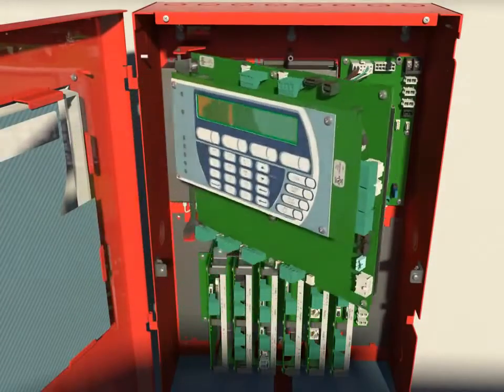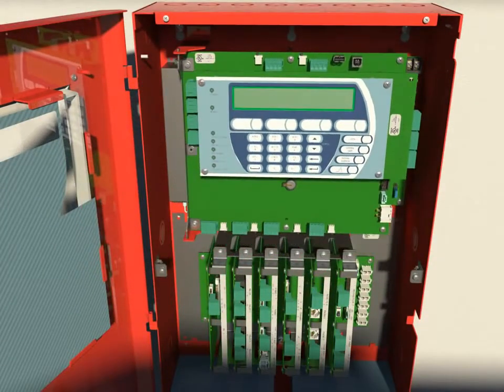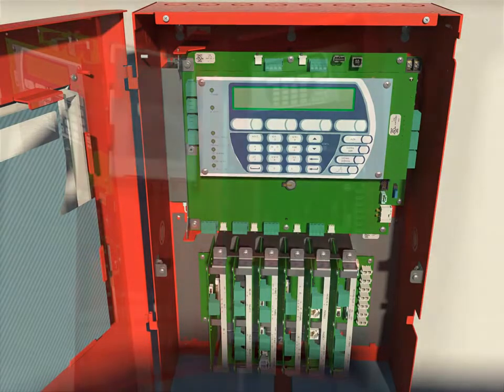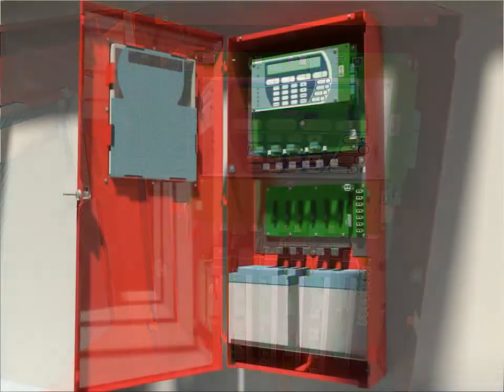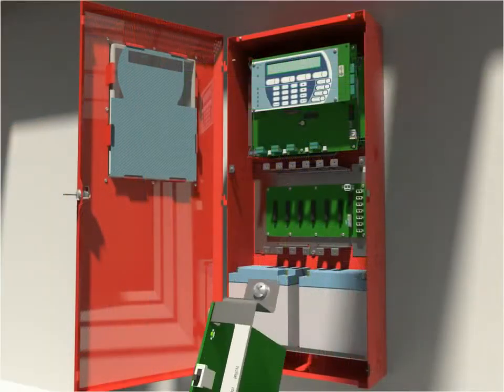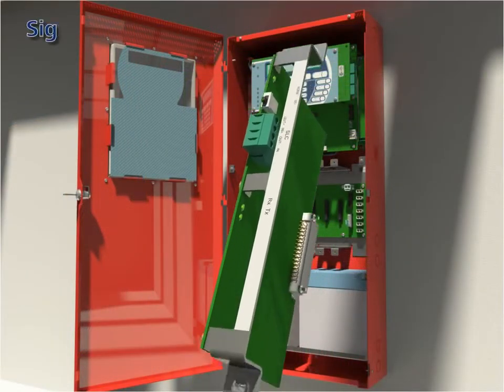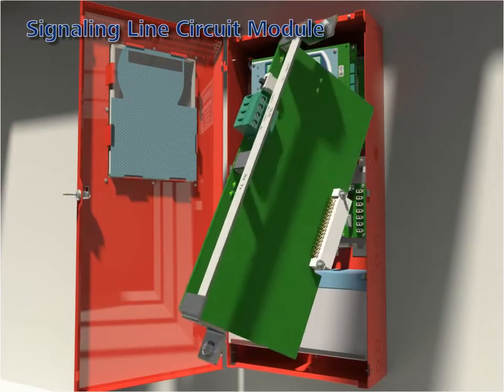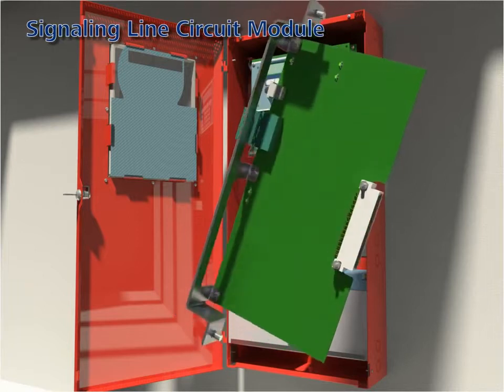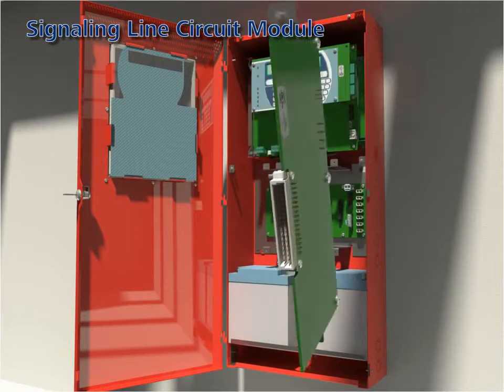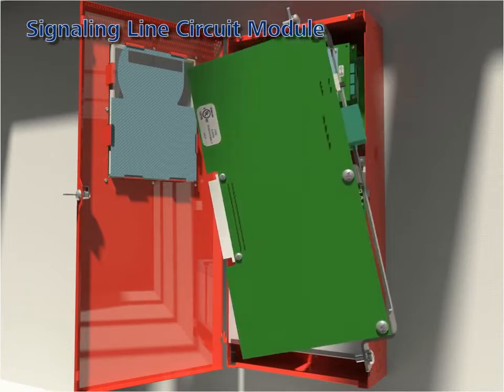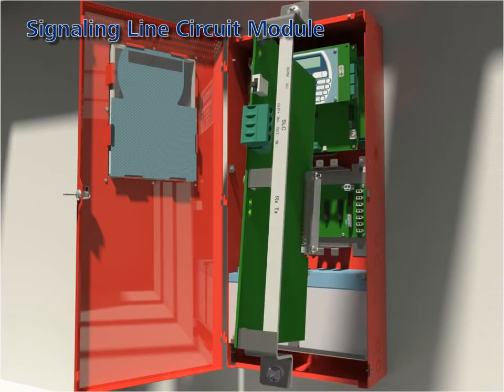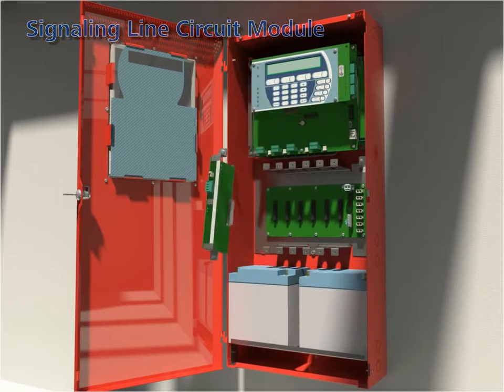The system offers exceptional expansion and functional capabilities through eight module types, 24 of which can be accommodated in a fully loaded system. Signaling line circuit modules: up to six can be added. Each module can address 255 devices with no device type restriction.